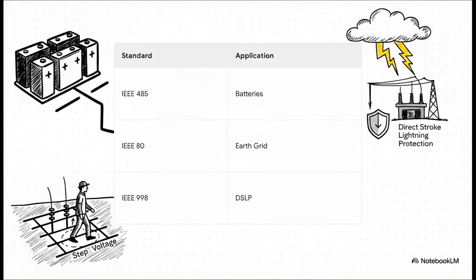As global industry professionals, we have to stringently adhere to these guidelines. We already touched on IEEE 485 for batteries, but IEEE 80 is your absolute Bible for earth grid design. It's how we calculate safe step and mesh voltages so that personnel walking in the switchyard are actually safe during a fault. And for the sky above, we rely on IEEE 998 for direct stroke lightning protection. Honestly, you simply cannot design a safe substation without mastering these documents.